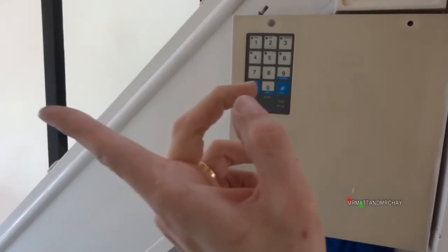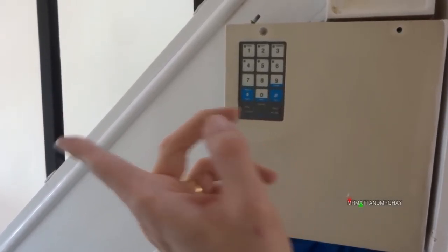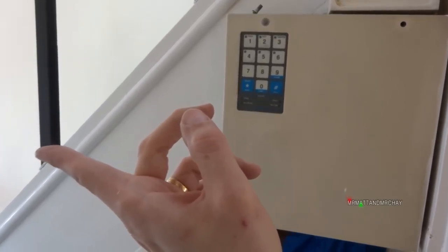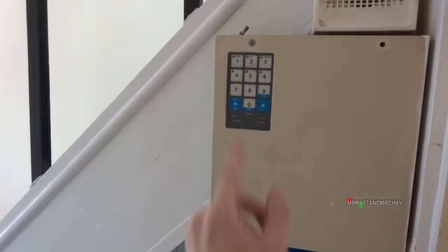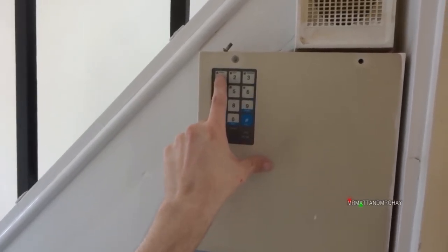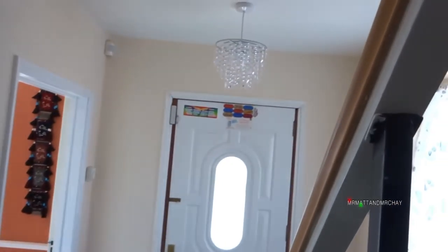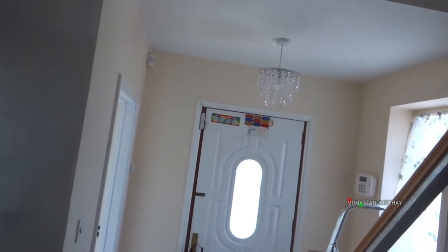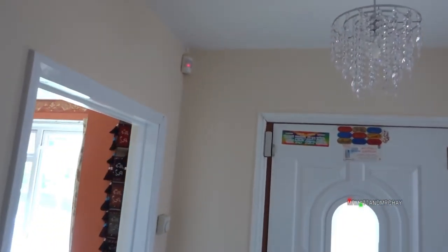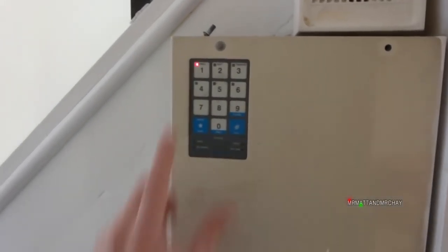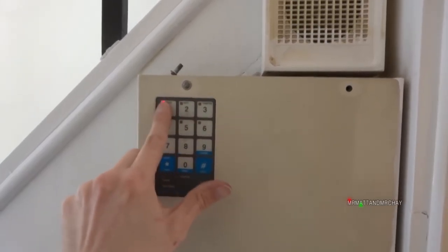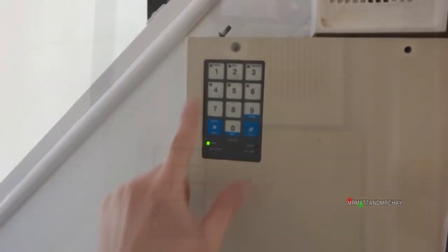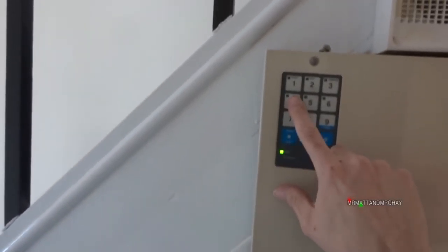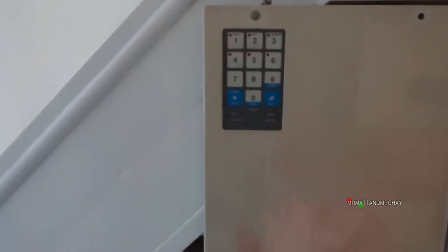The hall PIR is wired in with the door contact, although the door contact's currently disconnected. So if I move in the hallway, it will trigger zone one, which is the final exit zone. Here we go. Okay, entry tone, 30 seconds. 4, 3, 2, 1. So that's full set working. Let's activate the alarm now. So 4, 3, 2, 1, full set.